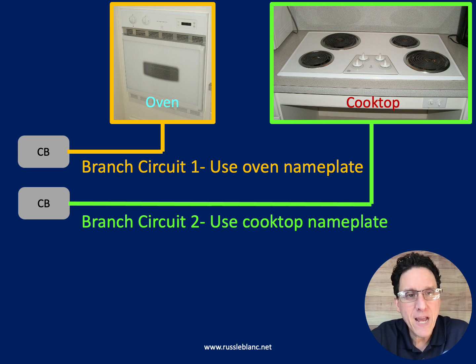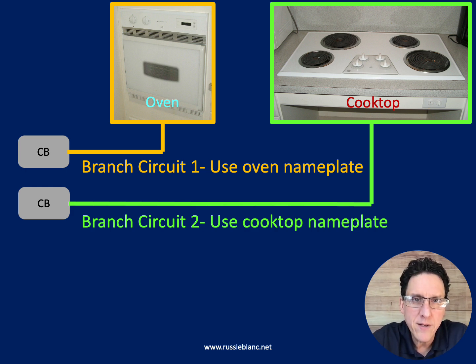But sometimes what might happen is, let's say you're doing a renovation, or the customer just bought a couple appliances, for example, right? And maybe you show up and the panel board only has space for one 2-pole breaker. And so you can't put 2 separate circuits in, right? That's a bummer. So you might be looking at adding a subpanel, or ripping out that panel and putting in a bigger one, for example. And well, the price just went way up for the customer, right? Just because you didn't have space for one more 2-pole breaker. There's another note we want to look at. So maybe we could use note 6.